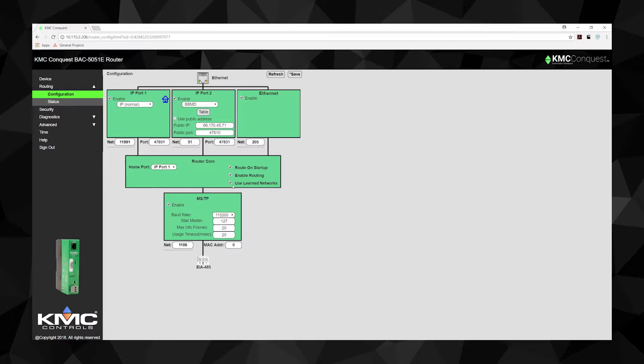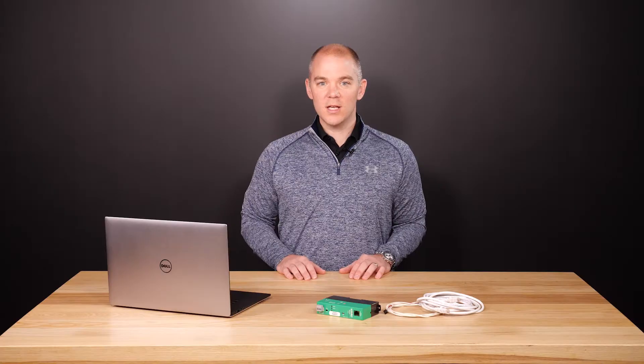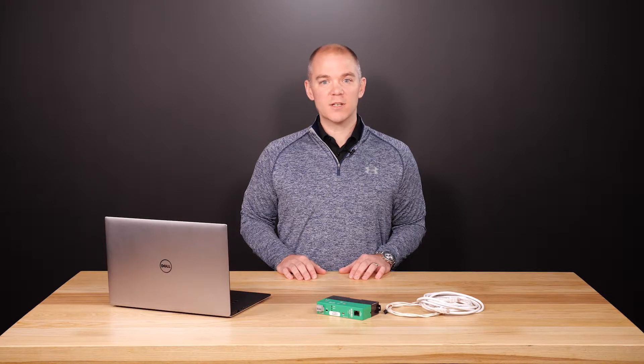When selected, the router will attempt to learn the network number in use on a port. One thing to note: Learn Networks only works if there is at least one other router on the network that responds to a BACnet 'What is my network number?' message. If a network is found, the router will use it; otherwise, the router will use the configured network number.